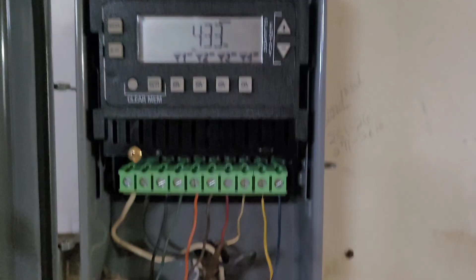I gotta put the covers back on it right away because it's pulling a lot of air through here, so it's probably gonna trip out on high limit. But that did fix the problem — now the blower is running and this system is cooling as it should.